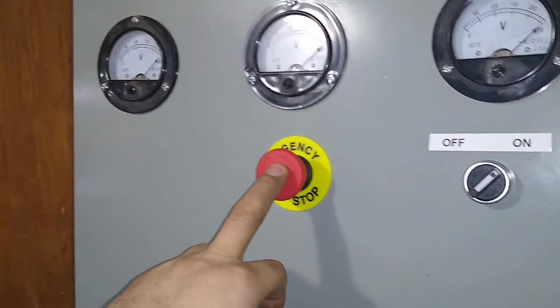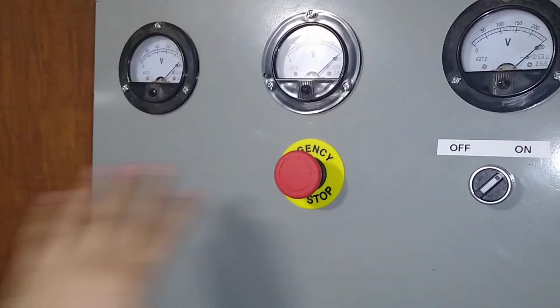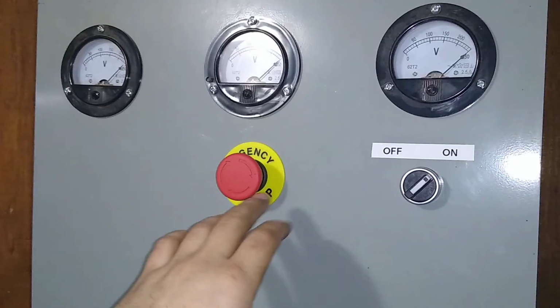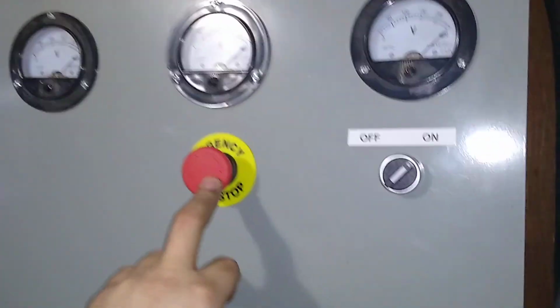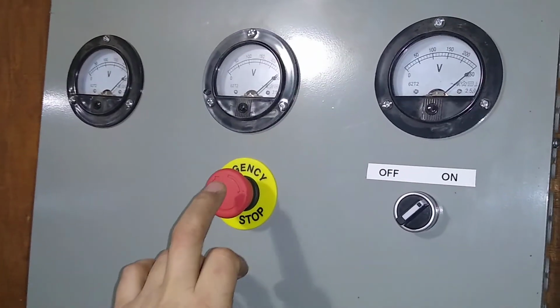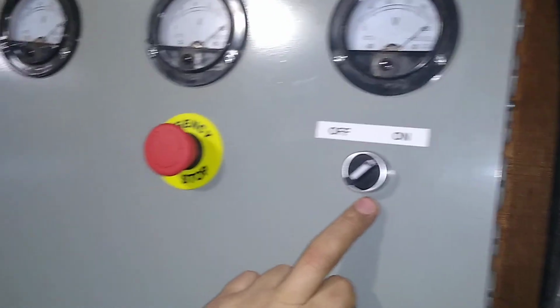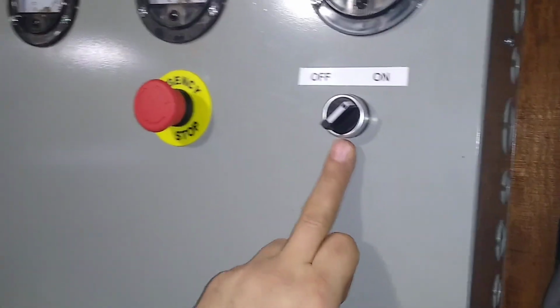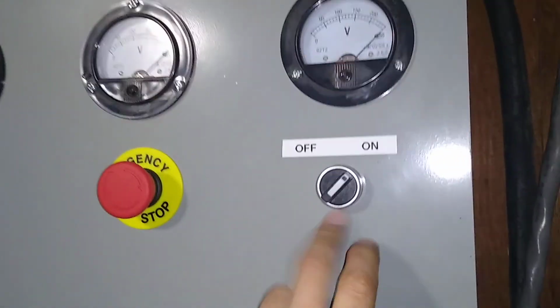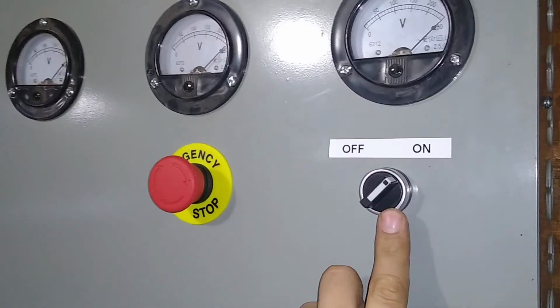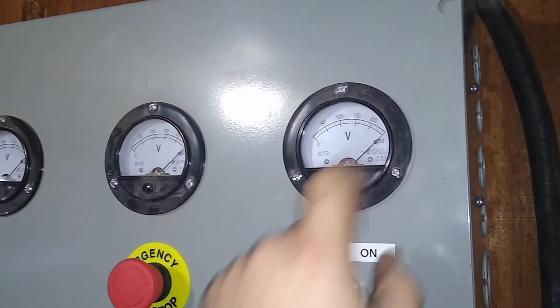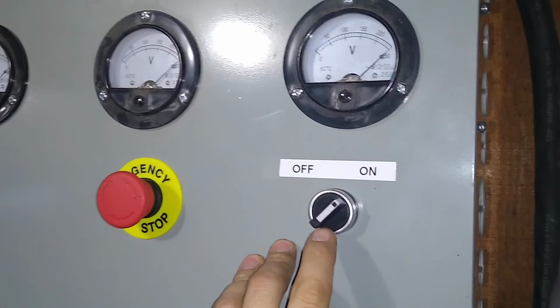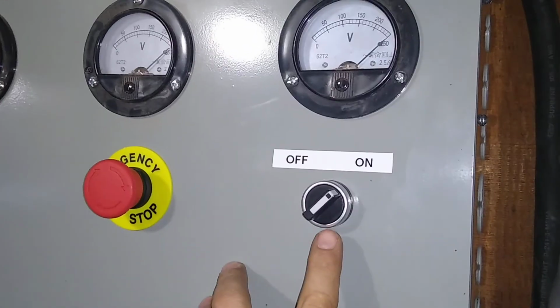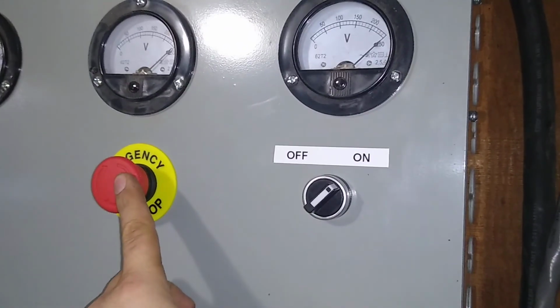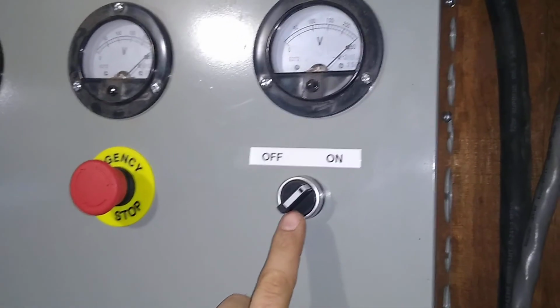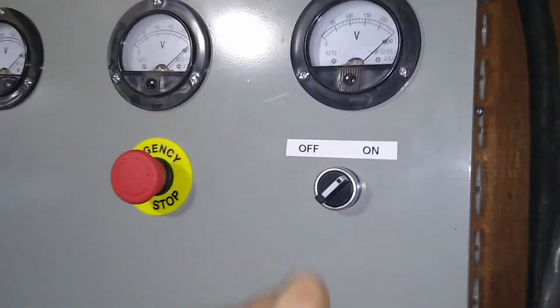All the e-stops are in series, so if I hit any e-stop, it shuts it off. To do that, it had to be wired in series, and then it was in series with my on and off switch. This is the only way I could think to do this. All my on and off switches are parallel to each other, but in the end, before it's fused, it's run in series with this. So if any of these stops are pushed in, none of the on and off buttons anywhere will work.